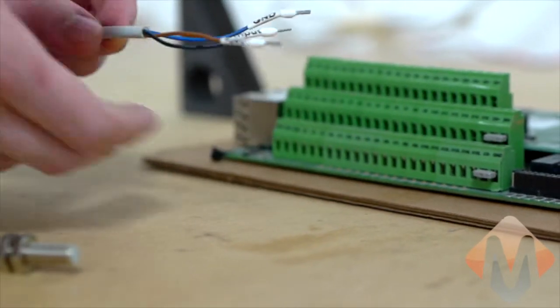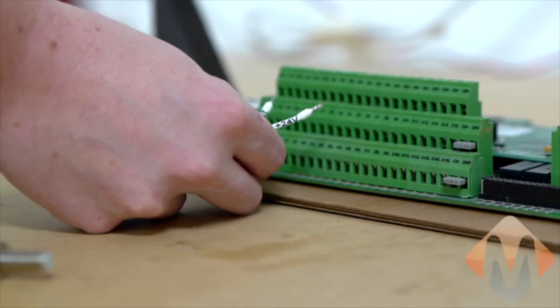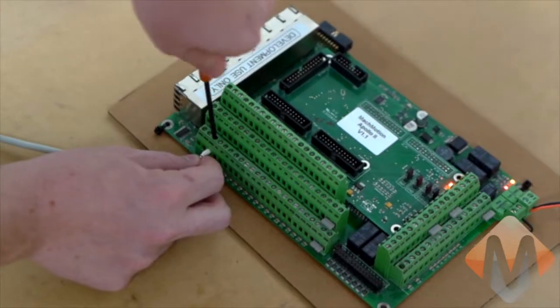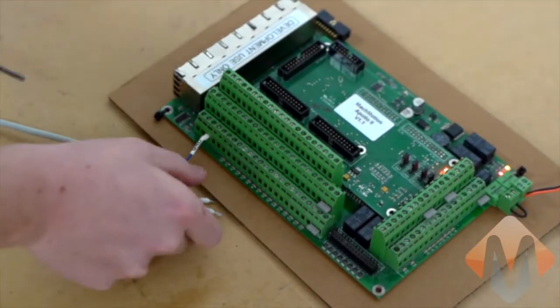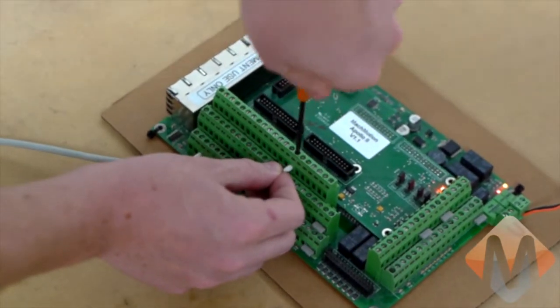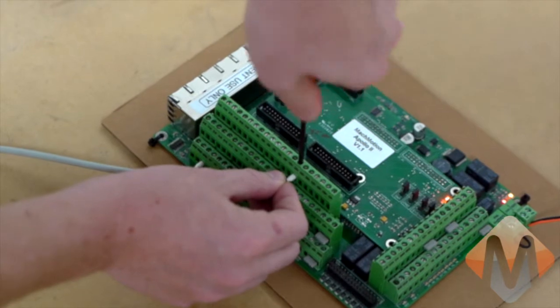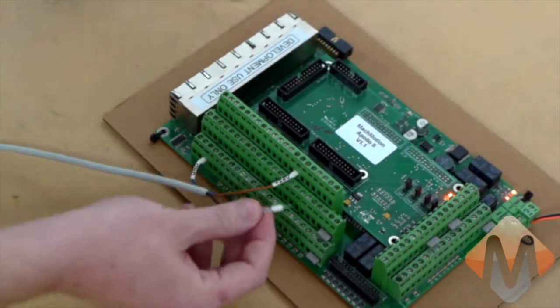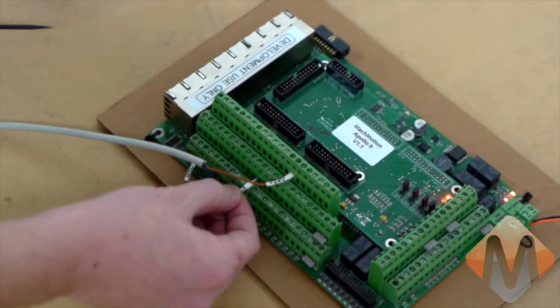To wire it in, there's going to be a ground, so we'll wire that to the ground terminal. You have a 24-volt input that we'll put into the C0 Plus bus. And then you have your signal, which we're going to wire into X5.